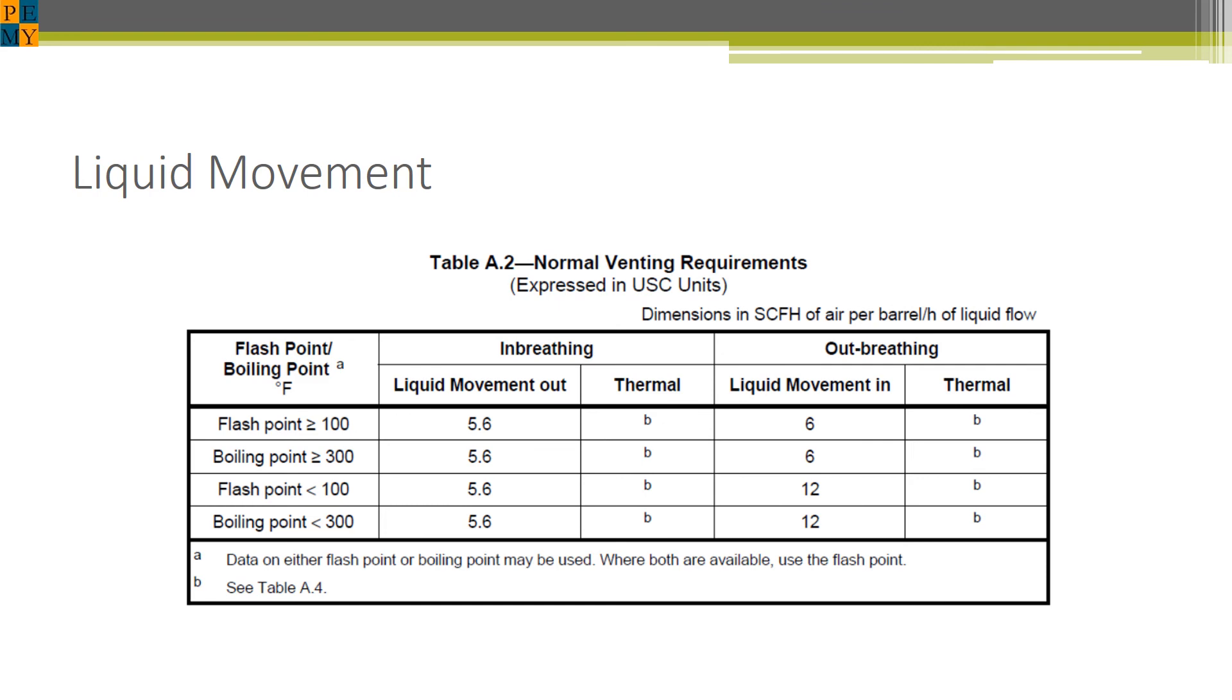To calculate the amount of venting required, we use this table where we use as an input the amount of liquid coming into or out of the tank in units of barrel per hour. We look up these factors that are dependent on the temperature, which determine whether the product is volatile or not. However, this is really just a unit conversion of the flow rate converting it from barrels per hour to standard cubic feet per hour.